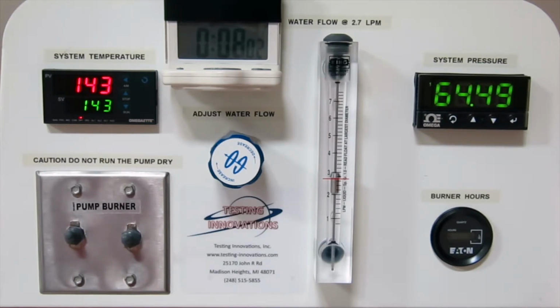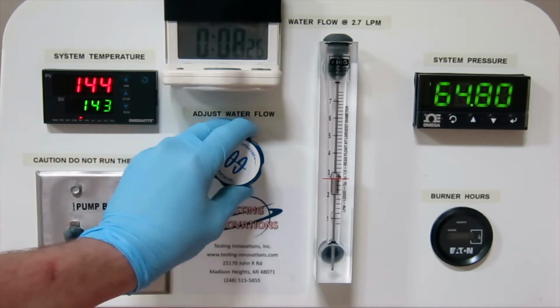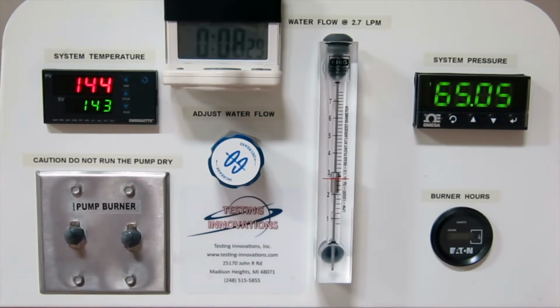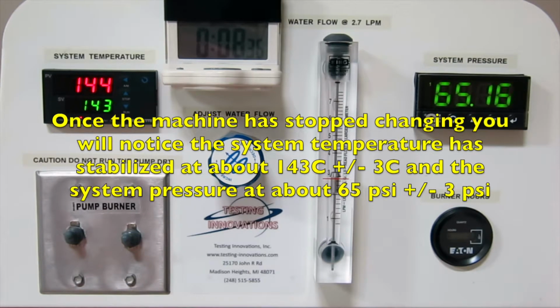You will now notice how the machine's running parameters are stabilizing. Once the machine has stopped changing, you will notice the system temperature has stabilized at about 143 degrees Celsius. You will also see the system pressure stabilize at about 65 psi.